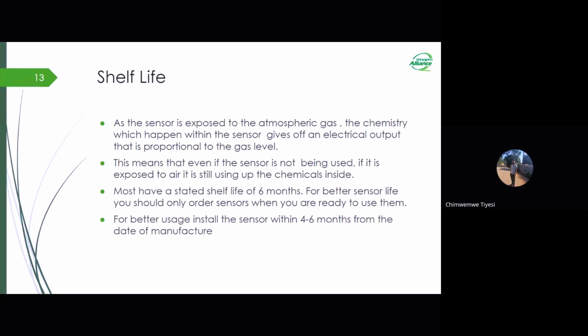So now I'll talk about the lifespan of the electrochemical oxygen analyzer. A normal oxygen sensor has a service life of up to 24 months, which is basically 2 years. At 25 degrees Celsius and 60% relative humidity, the sensor can last up to the stated 2 years. I just want to repeat here that regardless of whether or not the oxygen sensor is used, the life of the sensor starts to deteriorate immediately after its manufacturing date.